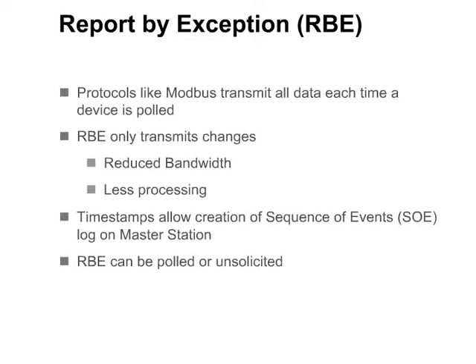More advanced protocols support report by exception, or RBE. Instead of reporting all data in the device, RBE only transmits changes or events of interest. This can result in reduced bandwidth and less processing, because only changed points are transmitted, resulting in fewer points being sent. Attaching timestamps to RBE data allows the master station to recreate the sequence of events that occurred in the outstation.